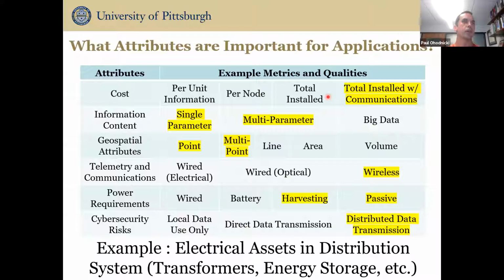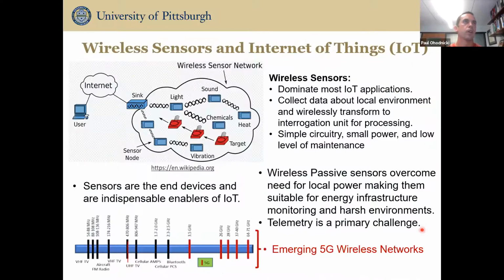If we look at transformers or energy storage, though, it looks very different. Now we have to worry about communicating with these because they're discrete devices on the system. We may be worried about just one parameter, like temperature, or multiple parameters. We're typically interested in point measurements, maybe multi-point, but since these are individual discrete devices, we're not as concerned about linear measurements. Wireless telemetry tends to be most compatible because we're not just sending information from point A to point B, but accumulating it from a number of distributed devices in the system. Again, passive power is preferred, and we have to worry about distributed data transmission. This is one reason why, for transformer monitoring or electrical asset monitoring, cybersecurity becomes extremely important, because we have to find a way to either use the data locally or accumulate it.